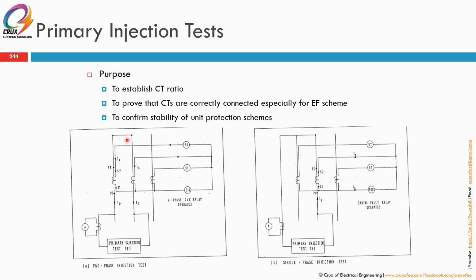So you will check for red, yellow, return, then yellow, blue, then red, blue, and then you know that you can confirm whether the connections and the polarity are correct for the CTs.